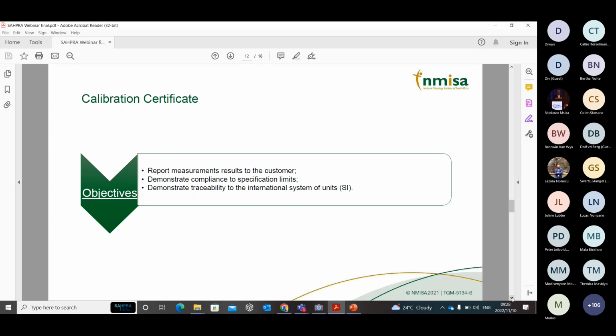So after the calibration, we actually need to give a report in the form of a certificate. And if we have been performing tests, then we will give a test report. Why do we have to give this report? The reason is that we need to report to the customer the results of measurements that we have obtained. We also need to demonstrate in that certificate that the instrument is complying with the specification limits. And we also need to demonstrate traceability to the international system of units, which is the SI units.